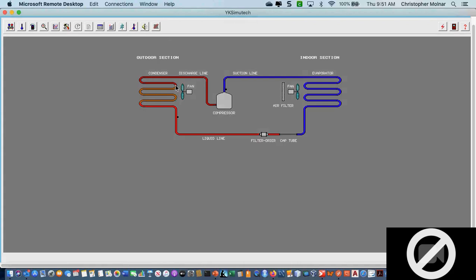If I have refrigerant at a higher temperature with air being blown across it at a lower temperature, where is the heat going to go? It's going to leave the refrigerant and go into the outside air. As I lower the temperature of this high pressure refrigerant, this gas coming out is going to condense into a liquid. It comes out of the condenser as a liquid, comes back through the liquid line, back to the cap tube — we start our cycle all over again.